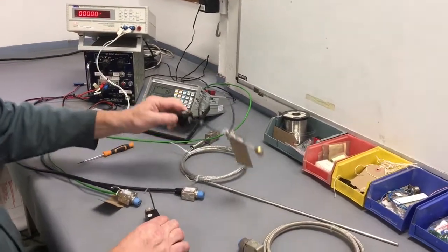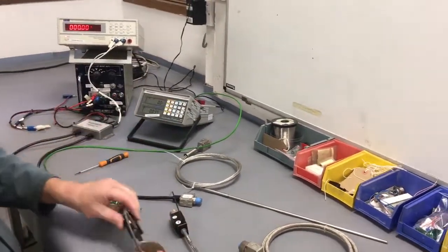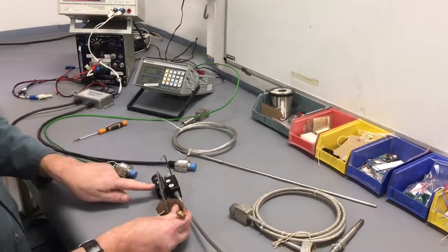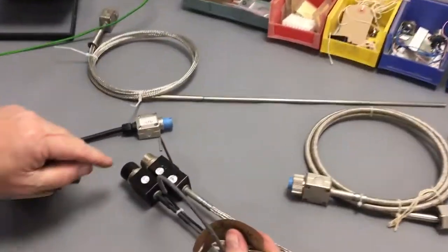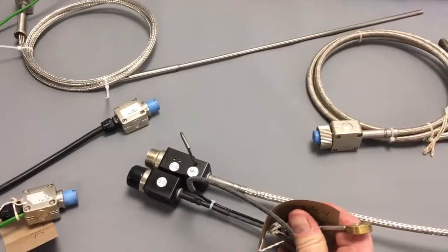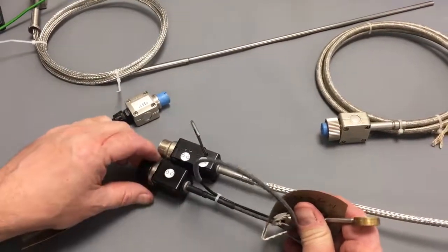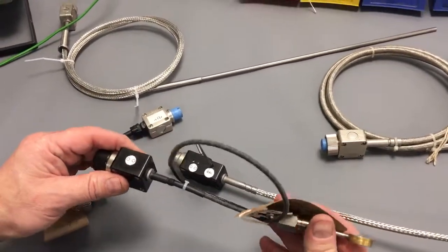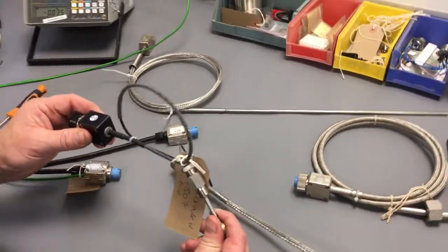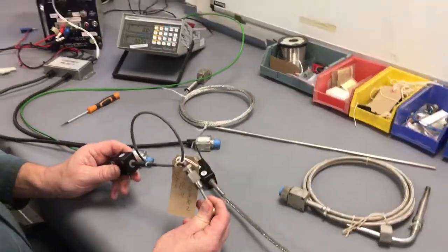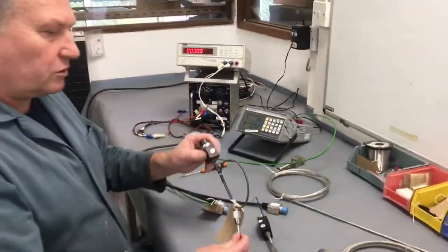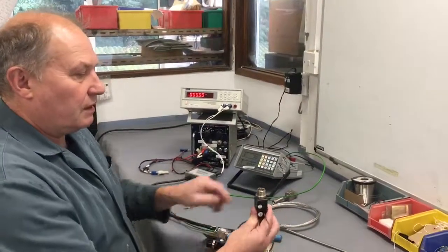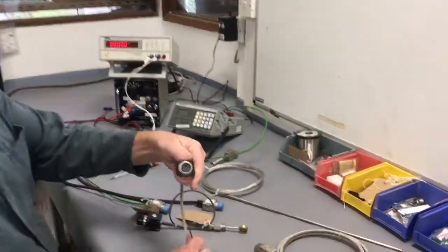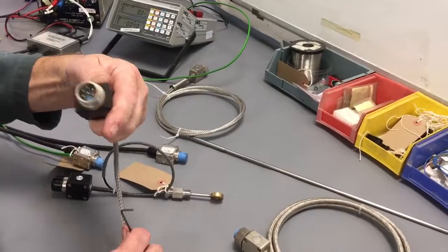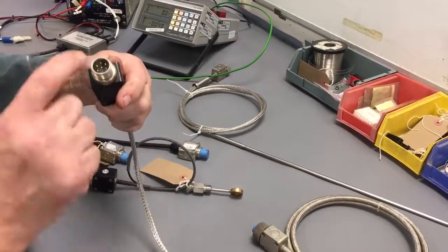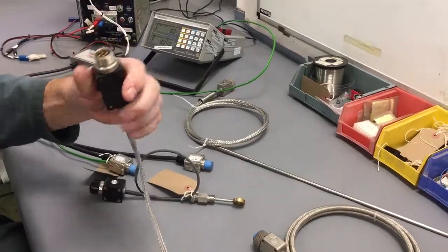The other alternative is to have the version without the switch, and you can see that the actual case is smaller. It's not possible to do a diagnostic test on this type of sensor, and this sensor requires calibration in a hot box or a calibration bath. Okay, hopefully that explains how things work, and you can see that the sensor is fitted with male pins. Obviously when it's disconnected there's no risk of any short circuit.